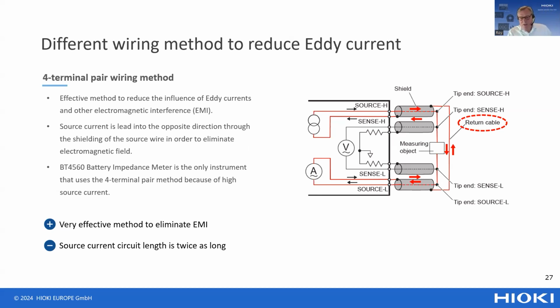Because of this, the BT4560 uses a 4-terminal pair wiring method. An important difference between the 4-wire and the 4-terminal pair method is the use of coaxial cable. What we are doing in this wiring principle is that we are sending the source signal first through the core of the coaxial cable, and then it will pass the battery and return to the measuring instrument. And when it is returning to the measuring instrument, we send it through the shielding of the same coaxial cable.